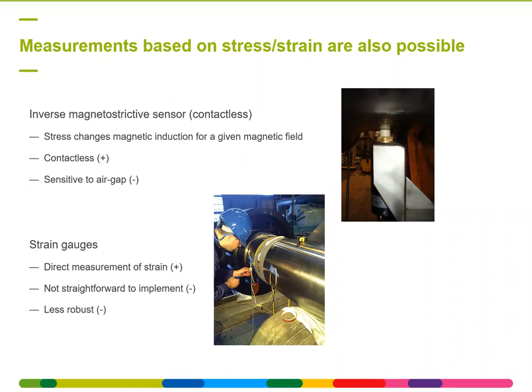Besides these pulse position based measurements, where you generate pulses, you also have measurements which are based on stress and strain. For instance, the top one, the inverse magnetostrictive sensor, has been developed by Laborelec actually in the 80s, 90s. And this sensor is placed very close to the shaft, also within 1 millimeter, and it senses a stress change of the material. So when the material is stressed, you change the magnetic susceptibility of the material, and actually this changes the magnetic induction, and so this is sensed by the sensor. So the advantage of this sensor is that it's contactless, it's a direct stress strain measurement. The disadvantage is that it's sensitive to the air gap.